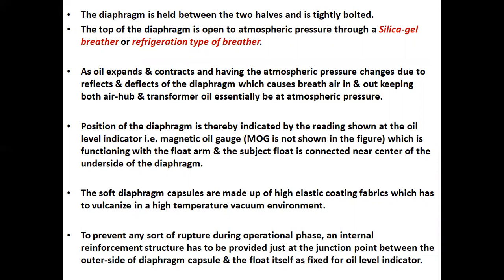As oil expands and contracts and the atmospheric pressure changes, due to reflex and deflex of the diaphragm, which causes breather air to breathe in or out, keeping both air hub and transformer oil essentially at atmospheric pressure.